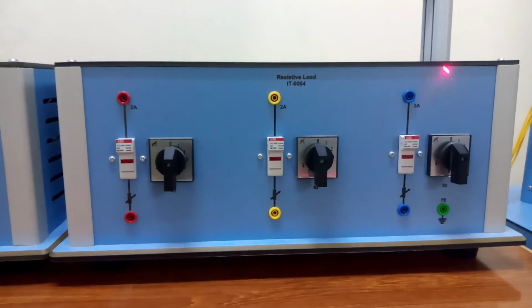Okay, so first of all, what we have to do is connect our 3-phase supply to this 3-phase transformer. It's very easy: you connect the red, yellow and blue phases to this transformer. So this is the red phase. You can see the connection is at the 380, because this is for the delta.